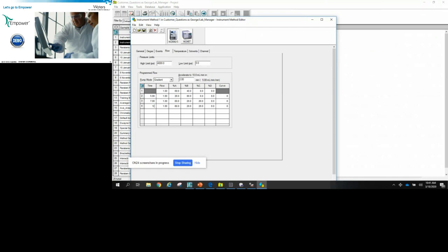And when an injection begins, there's a clock in Run Samples that counts from 0 to the run time. Every time the system makes an injection, it triggers that clock, and it goes back to 0 and starts over again. But after the last injection, there's nothing to trigger the clock. So if I'm at the end of the sample set, or if I'm stopped on fault because of a SysSuit failure, there's nothing to trigger the clock. The clock keeps recording time.